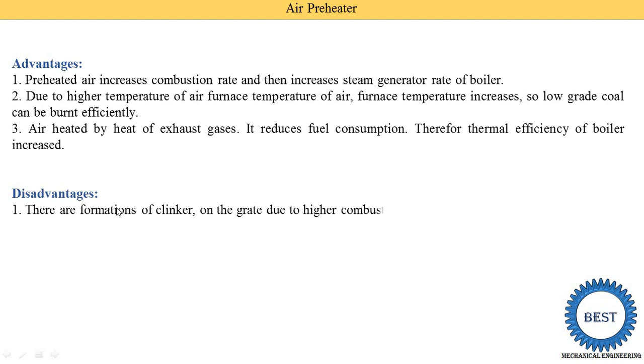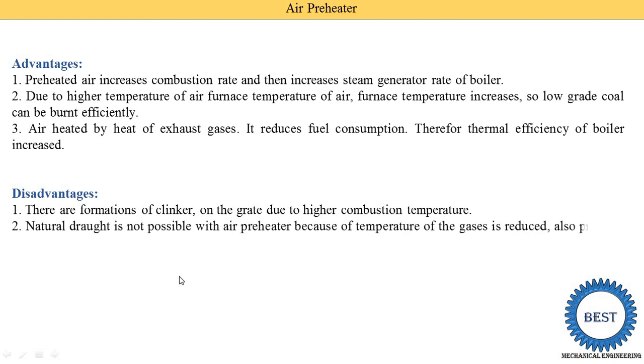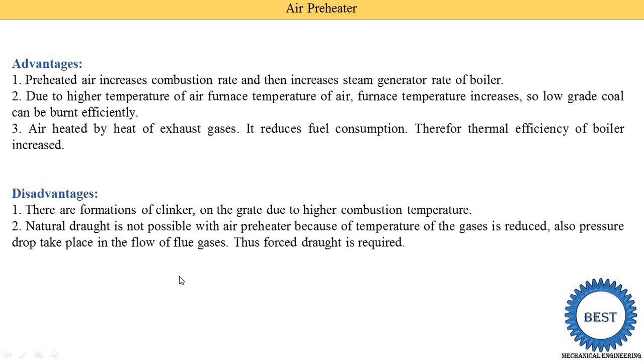The disadvantages are: there is a possibility of formation of clinker on the grate due to the higher combustion temperatures. Natural draft is not possible with an air preheater because the temperature of the gases is reduced and pressure drop takes place in the flow of flue gases. Therefore, forced draft is required, meaning blowers or fans must be installed in the air and gas paths, requiring additional power.